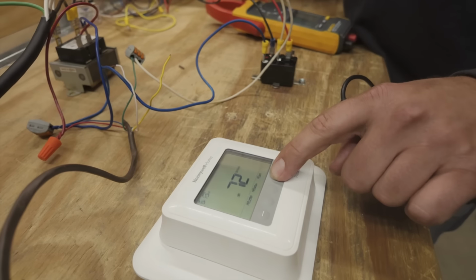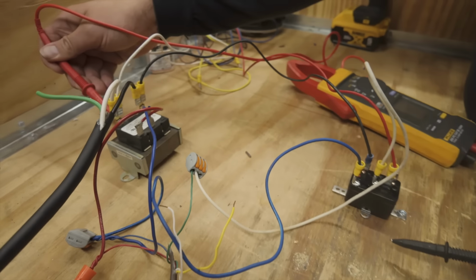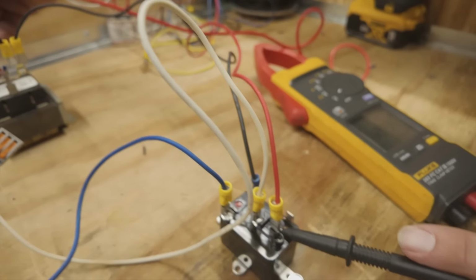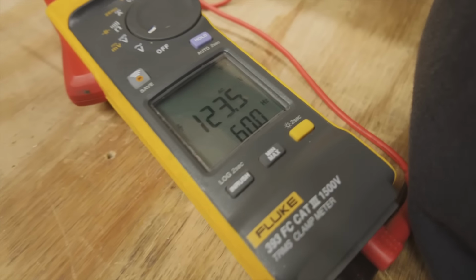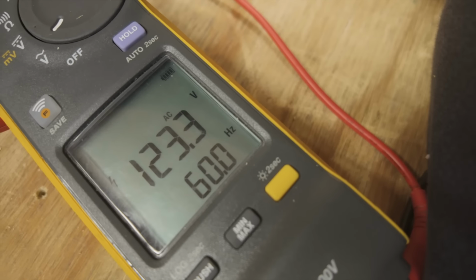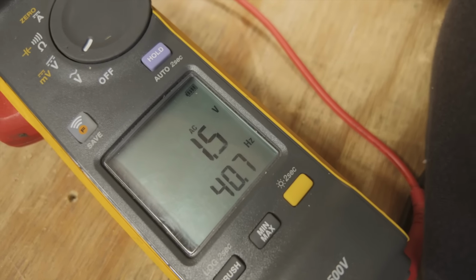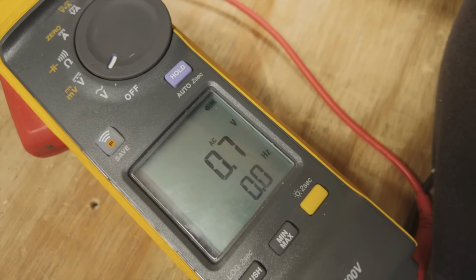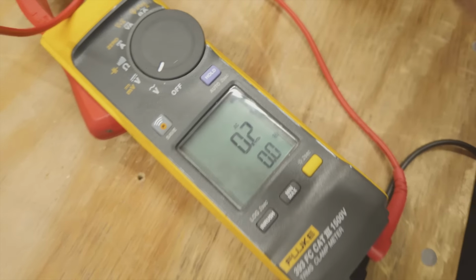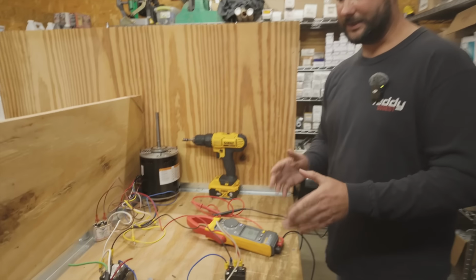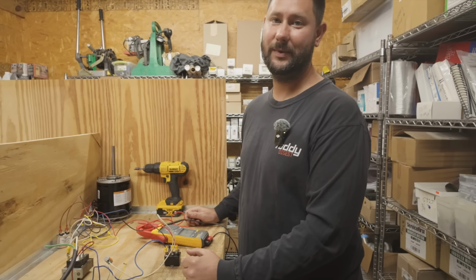All right, but if we take and turn it off, go back to this white, and then go to that side of the relay, what happens when we don't have a call? See, power's not going through that relay to that fan motor. That's how you check the fan relay.